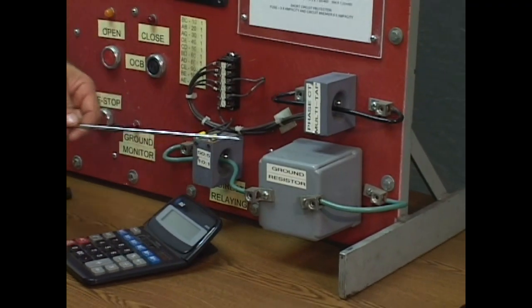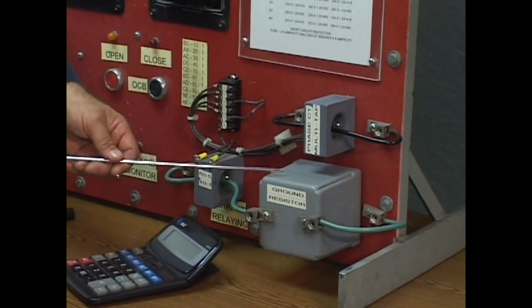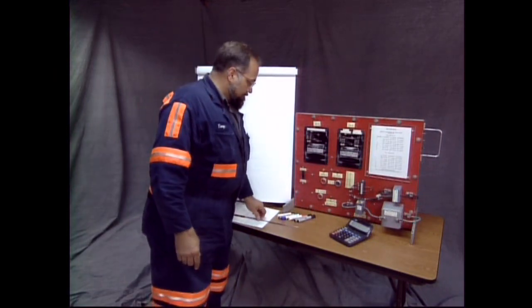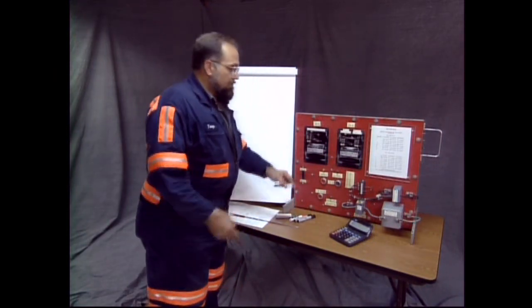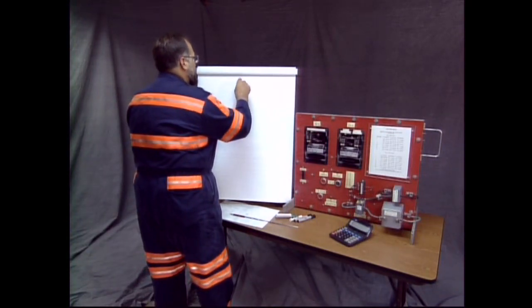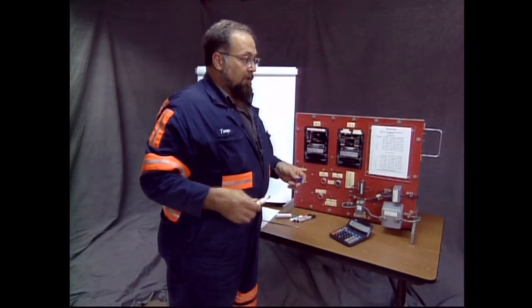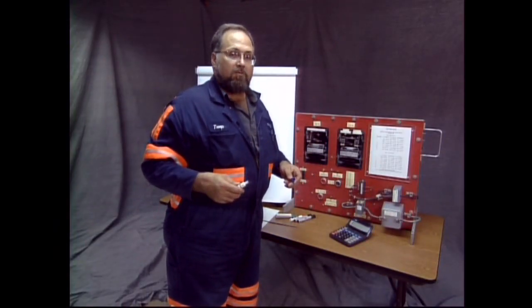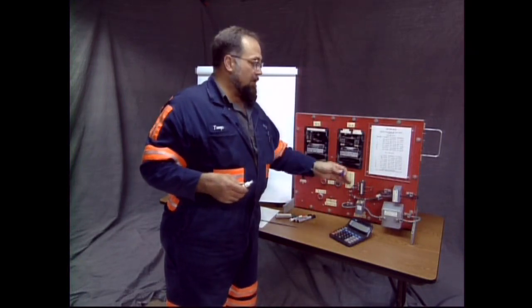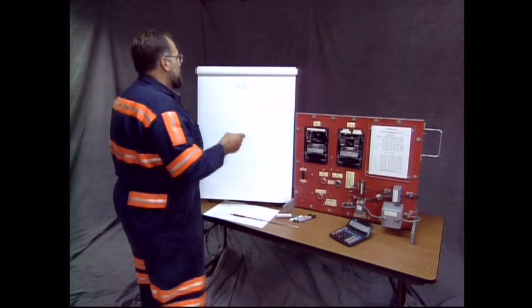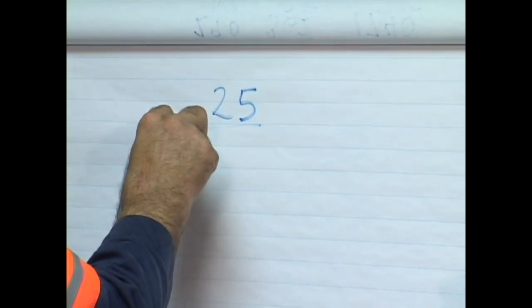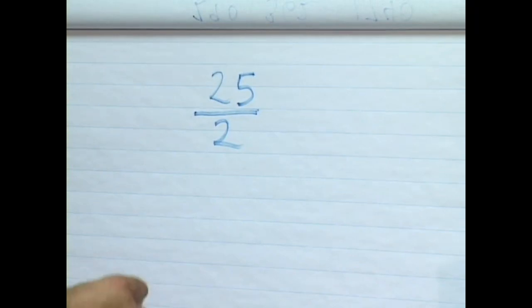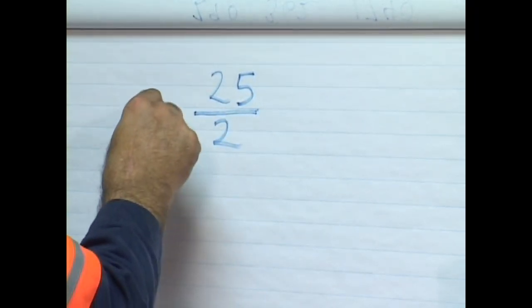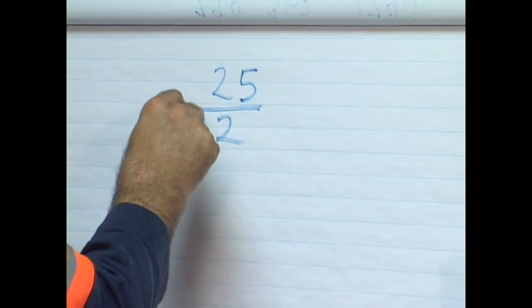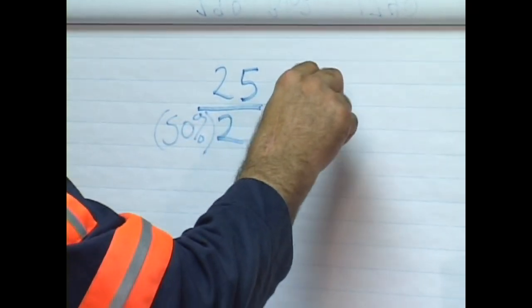There's only the ground resistor. There's not a great selection of cables here to choose from. There's one ground resistor, and mostly it's going to be a 25 amp ground resistor. As you can probably remember, I told you a maximum setting for the ground fault protection is 1/2 the ampacity of the ground resistor, 50%. So let's divide that by 2. 25 divided by 2, I'm going to make a little notation here, 50%, and that's going to equal 12.5.